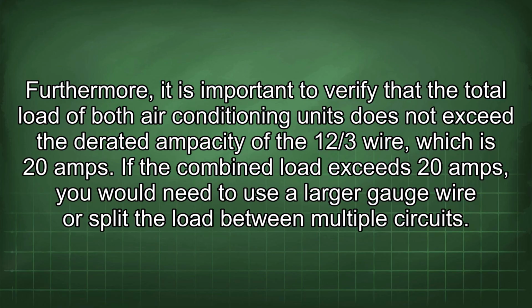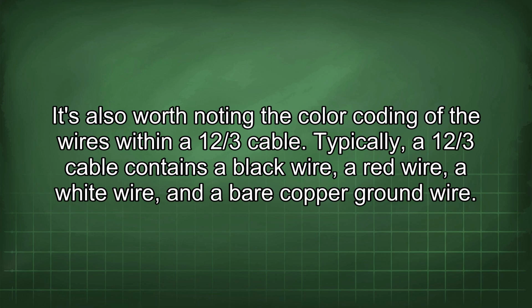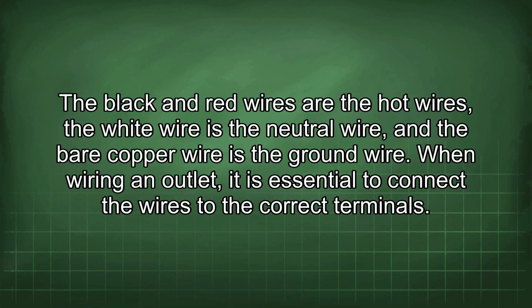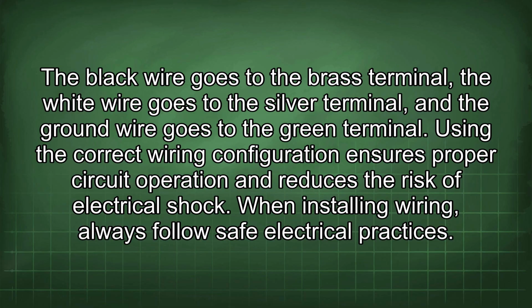It's also worth noting the color coding of the wires within a 12/3 cable. Typically, a 12/3 cable contains a black wire, a red wire, a white wire, and a bare copper ground wire. The black and red wires are the hot wires, the white wire is the neutral wire, and the bare copper wire is the ground wire. When wiring an outlet, it is essential to connect the wires to the correct terminals. The black wire goes to the brass terminal, the white wire goes to the silver terminal, and the ground wire goes to the green terminal. Using the correct wiring configuration ensures proper circuit operation and reduces the risk of electrical shock.